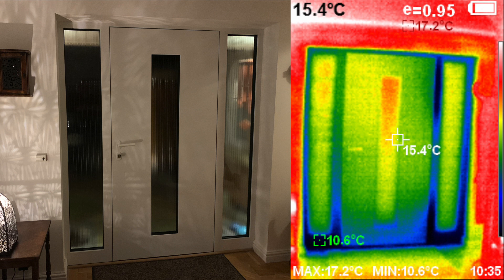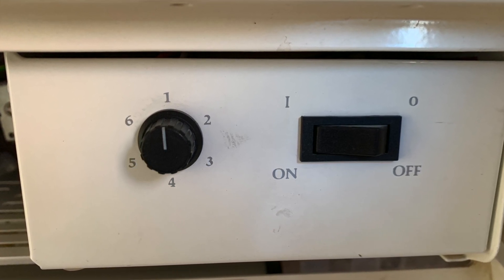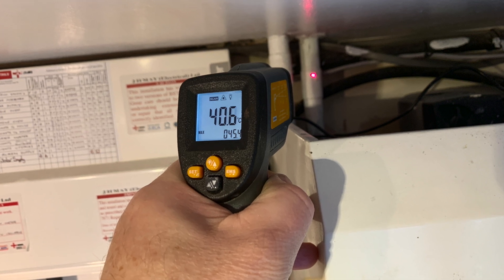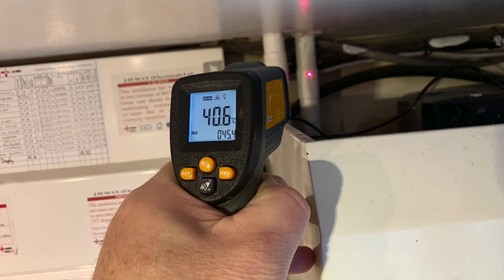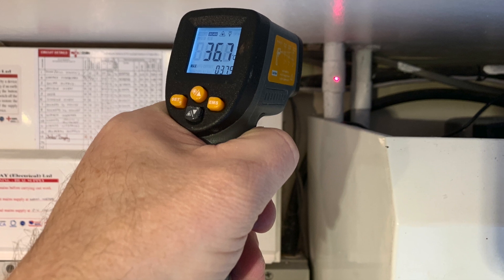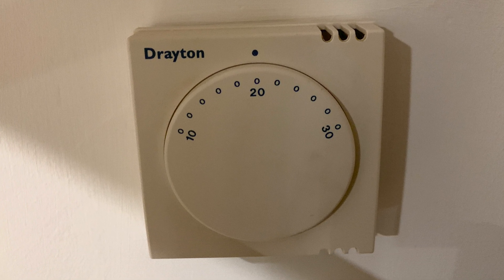Hence why we spent a large chunk of money on the front door. As a result of these changes we have turned down our gas boiler to number one — its lowest setting. It used to be on four, sometimes five, to keep the house warm. I've measured the flow and return temperatures of our central heating — outbound is now 40°C and the return flow back to the boiler is 36.7°C. We're using less gas than before these improvements even though we now leave it on 24/7 and set the temperature to 20°C for the radiators. The boiler just chips in and out, topping up the base heat.